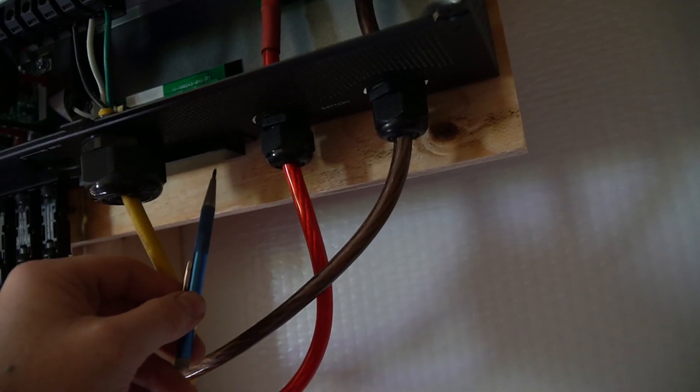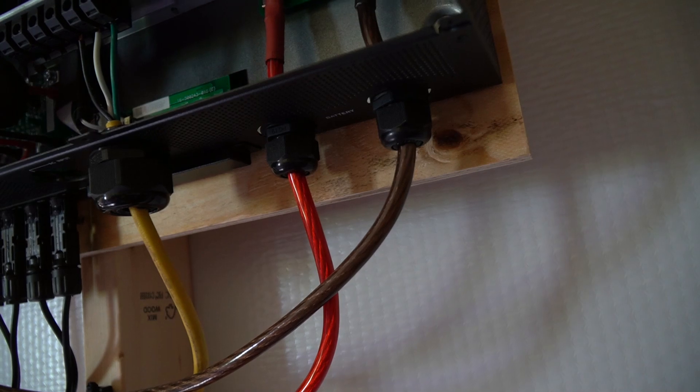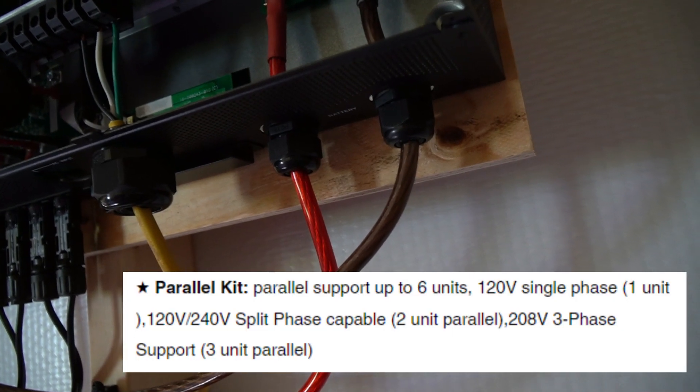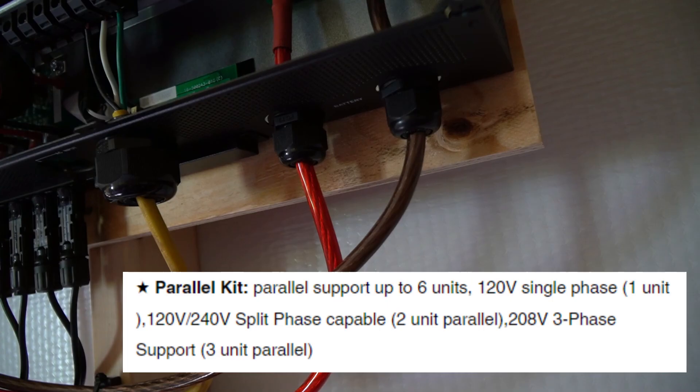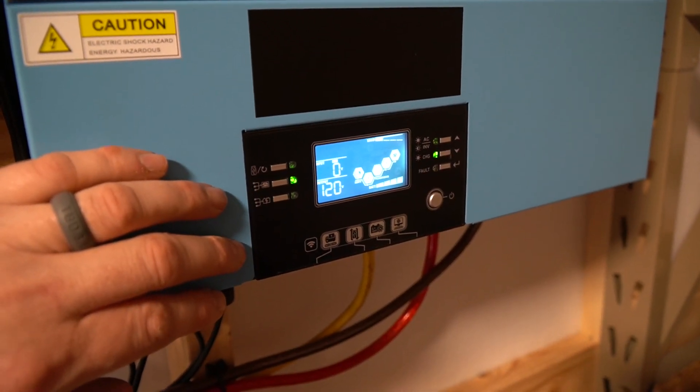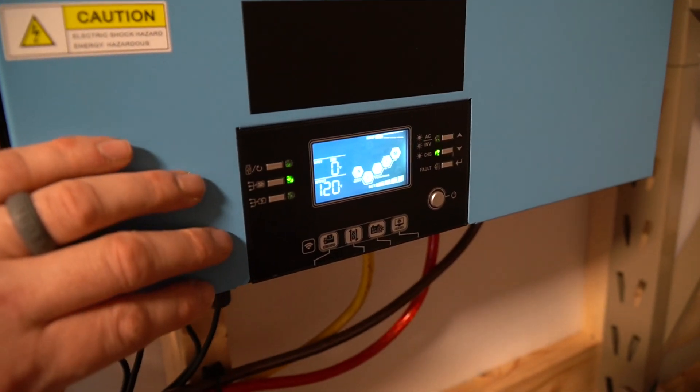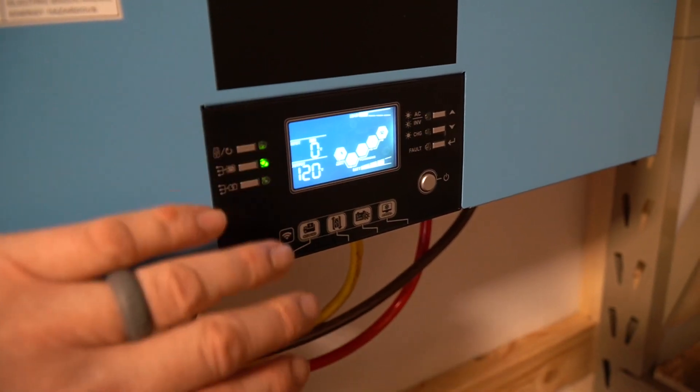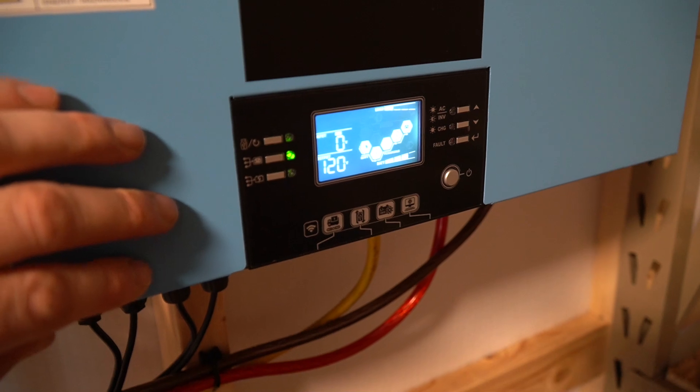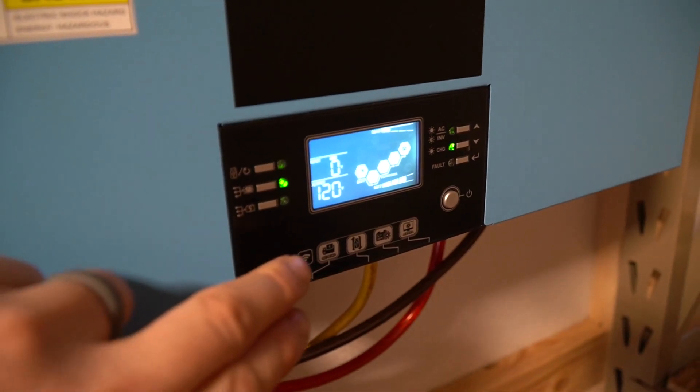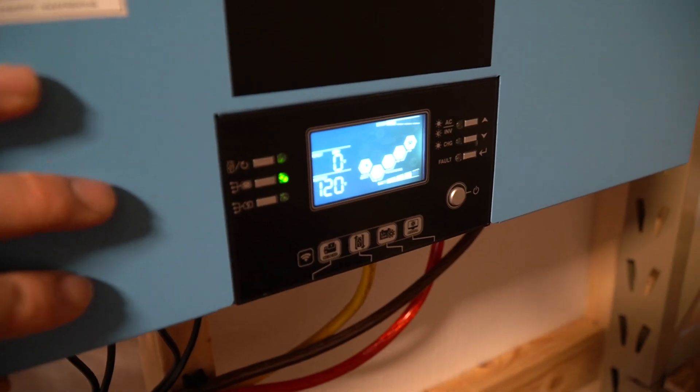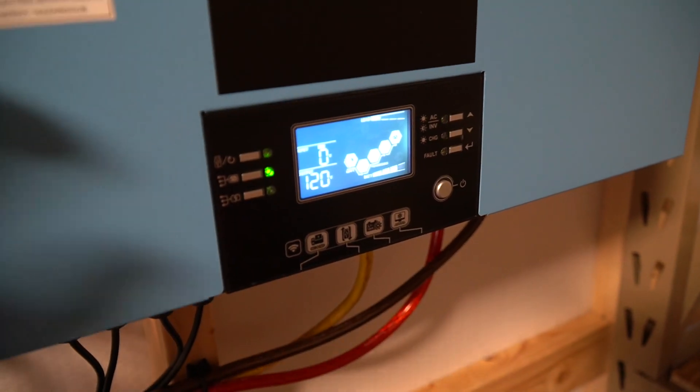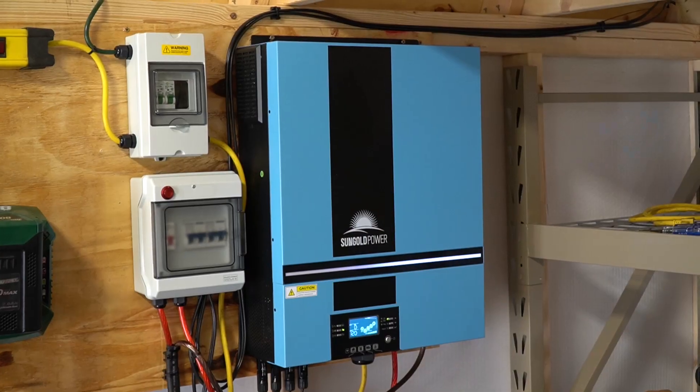Hiding underneath this cover is some more connectors that allows you to do a number of different things. You can parallel multiple units together. If you put two of them together, you can get a 240 volt system. The display and interface is actually quite amazing. You can configure every option through this display and you can take a look at all the stats. The display also slips out of here in case you want to mount it remotely. So if you were to put this maybe in a basement and you wanted to put this upstairs in your living area, you could totally do that. The connector uses a standard network cable, so it's really not difficult to extend this display if you need to.